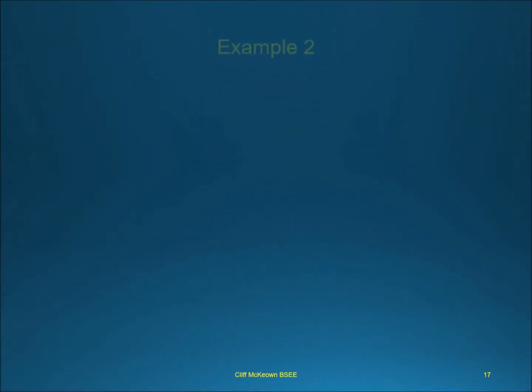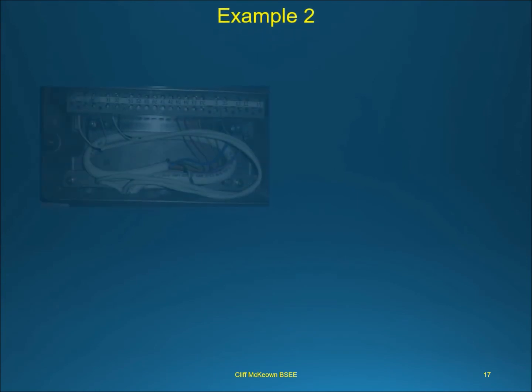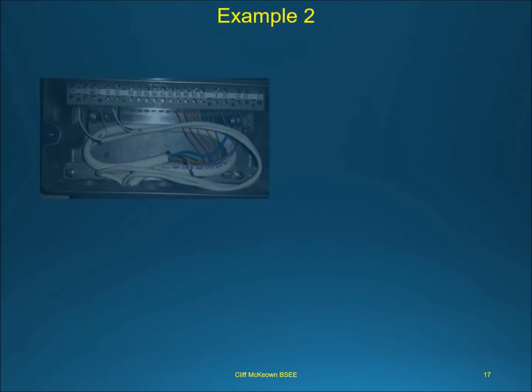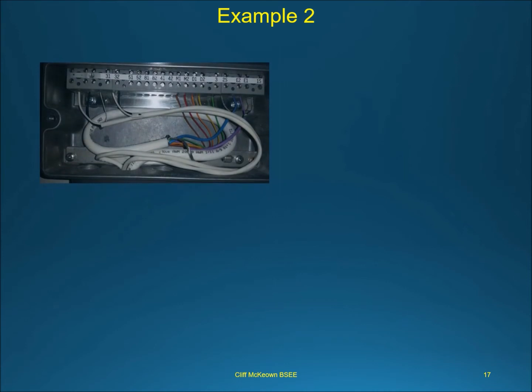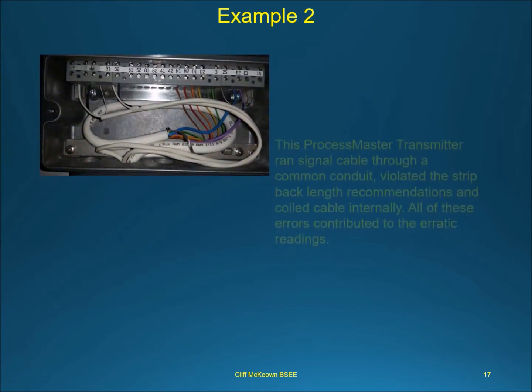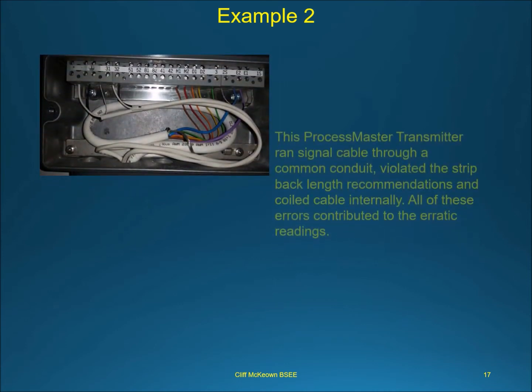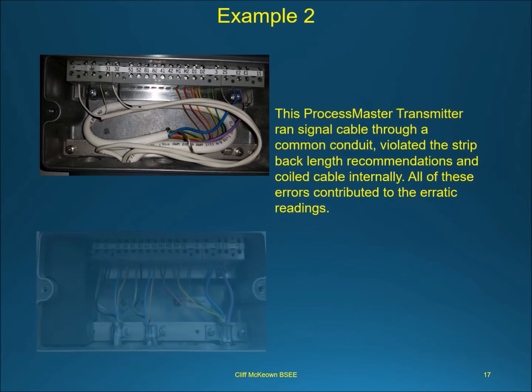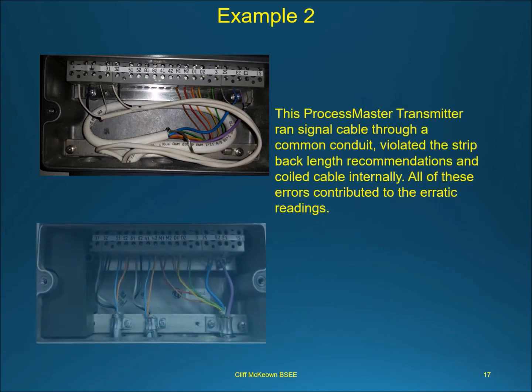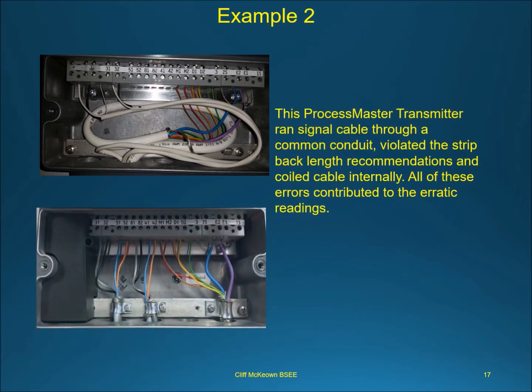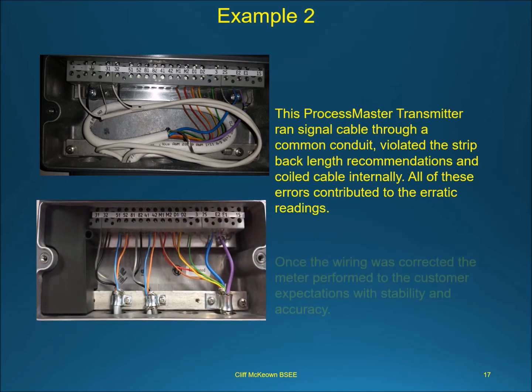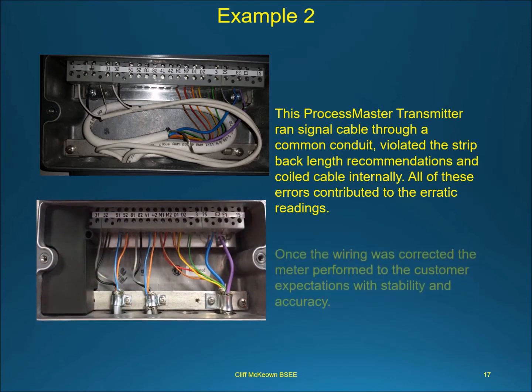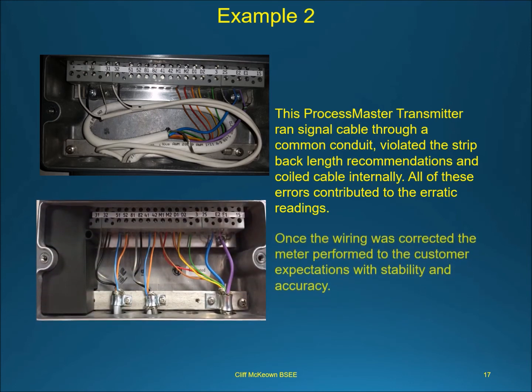Example 2. This Process Master transmitter ran signal cable through a common conduit, violated the strip-back length recommendations, and coiled cable internally. All of these errors contributed to the erratic readings. Once the wiring was corrected, the meter performed to the customer's expectations with stability and accuracy.